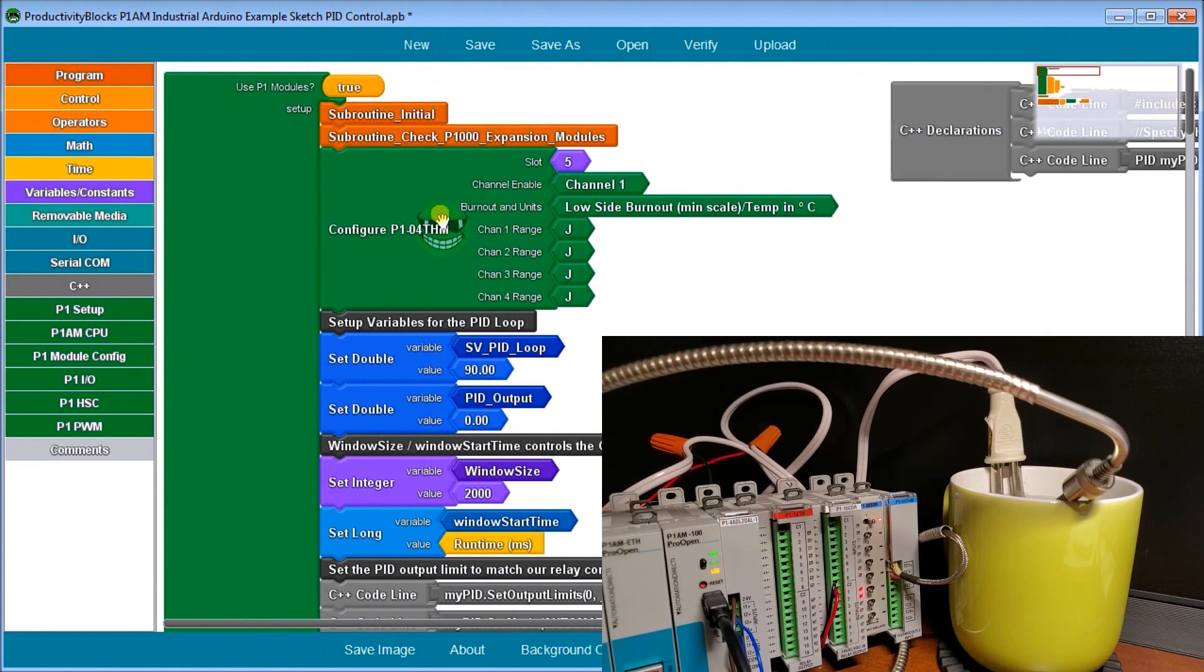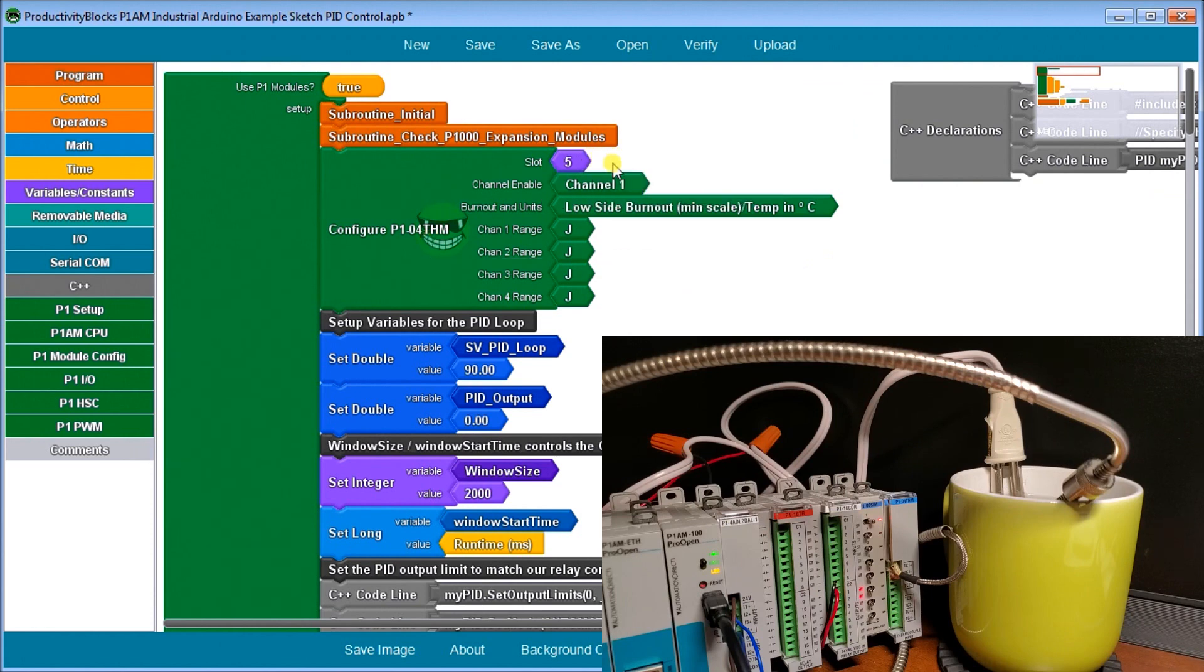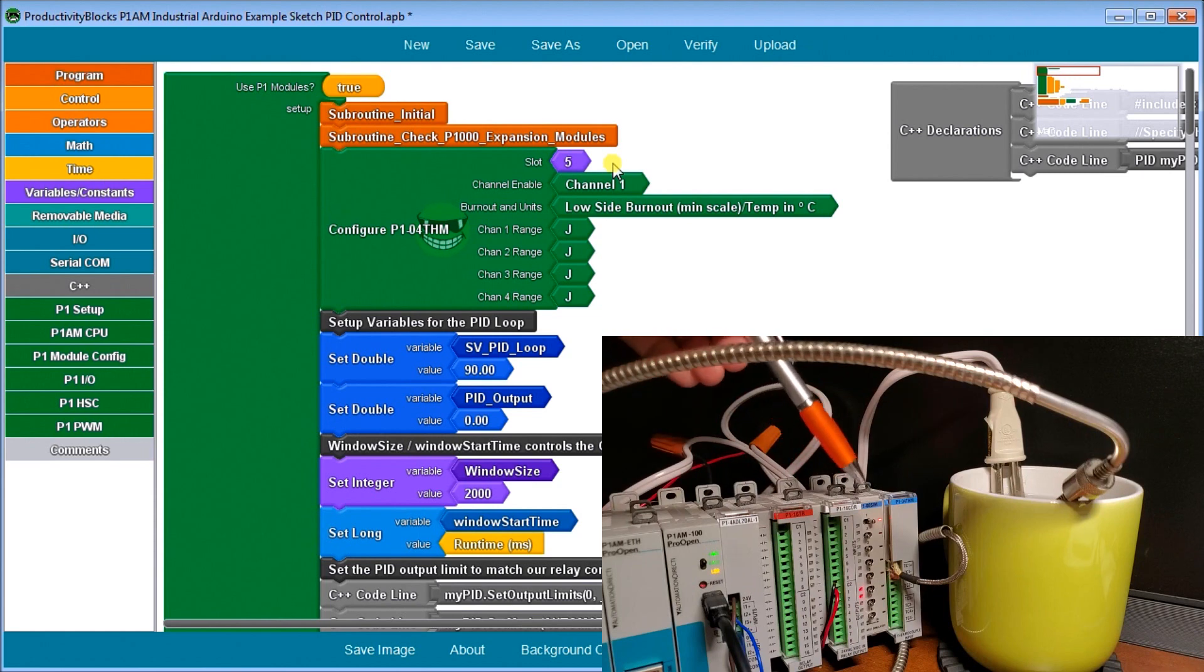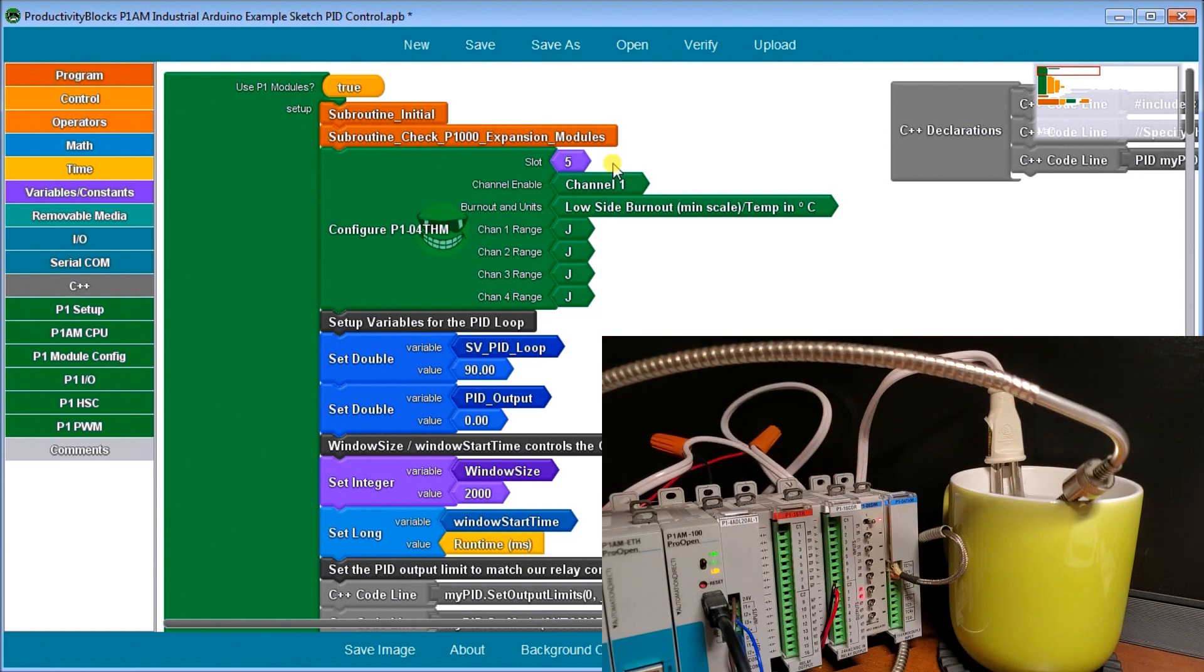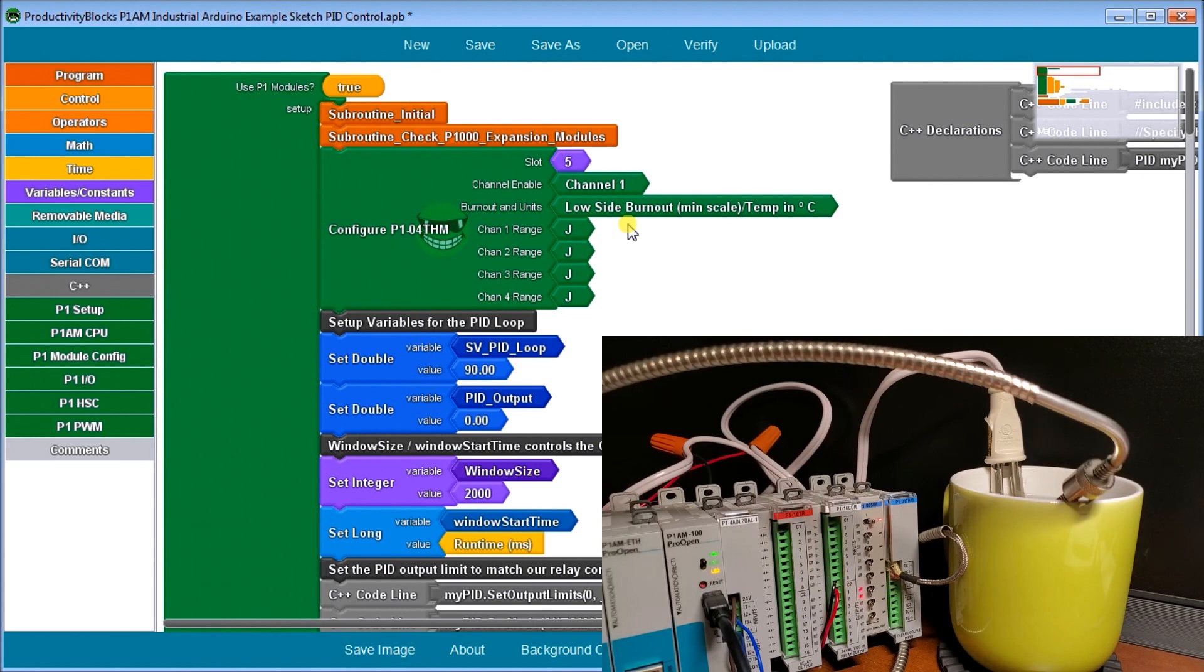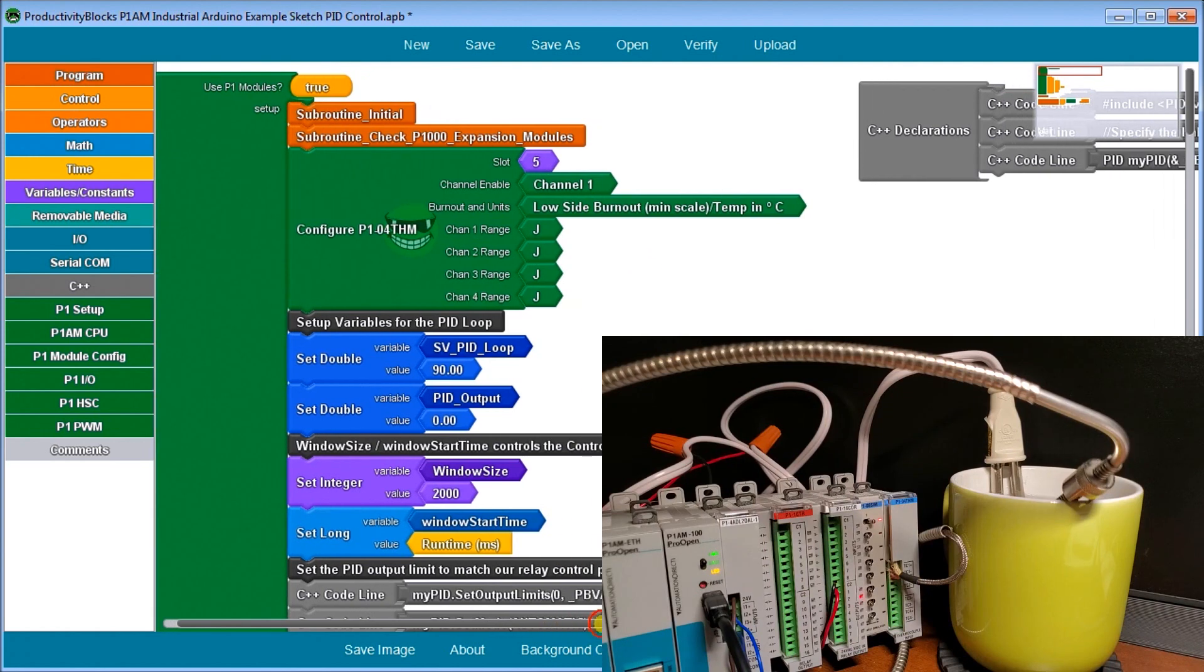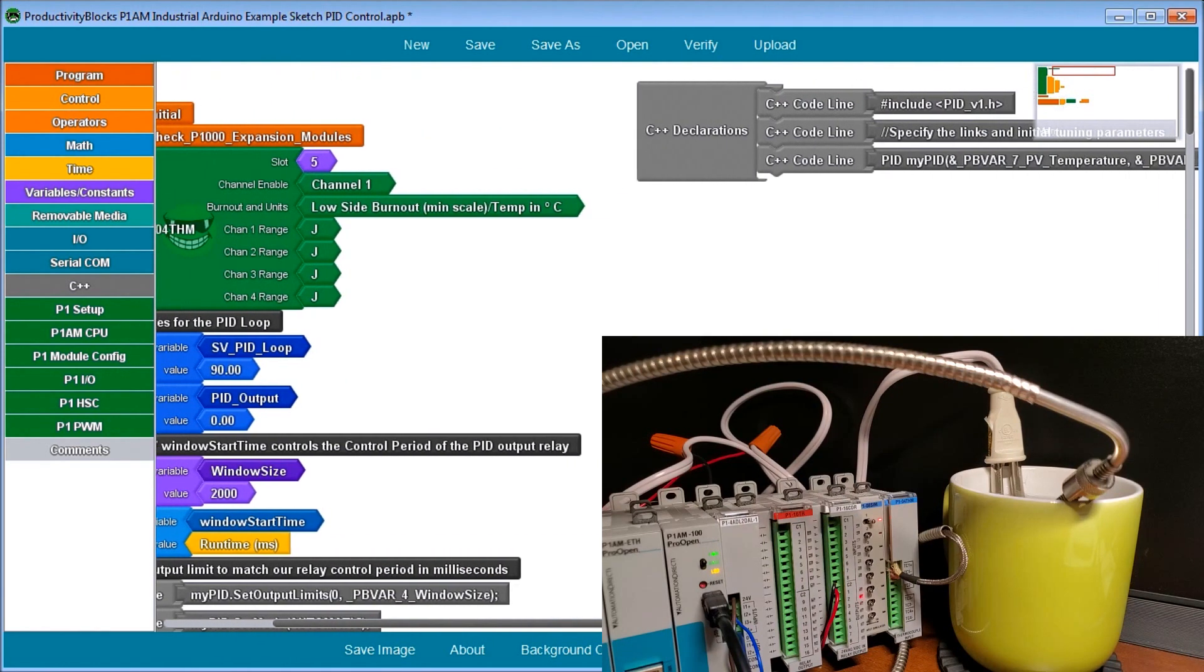So that is our loop there. Then we have our configuration for our thermocouple card. So slot number five. And once again, we get the slot by the unit number. We're looking at channel one and we're saying if we have a burnout, then we go to the minimum scale of our output. It's in degree C. And our input one channel is a J type thermocouple. So that is part of that setup.